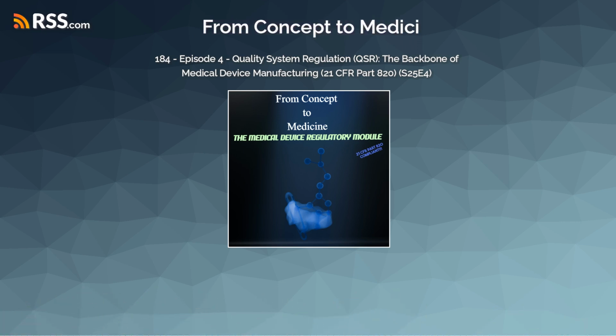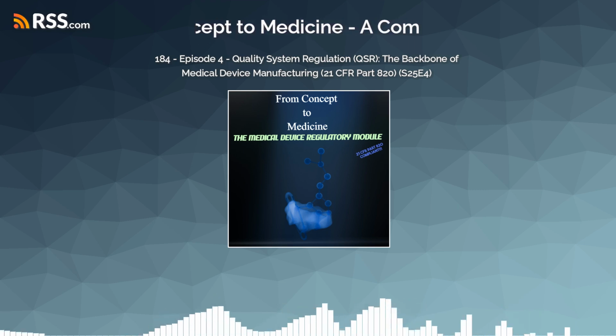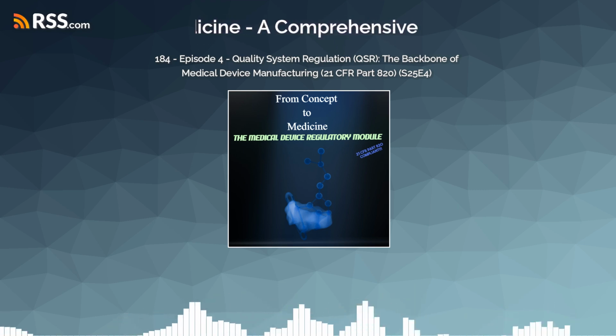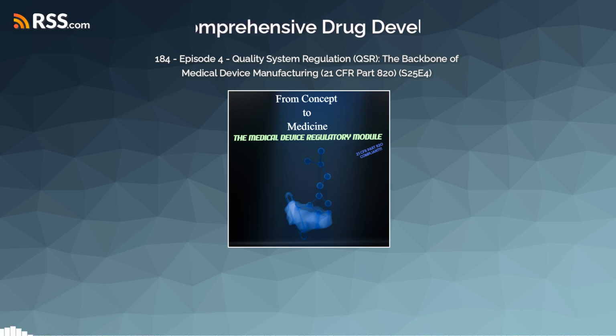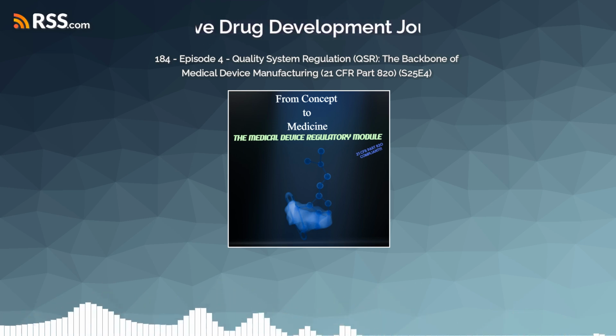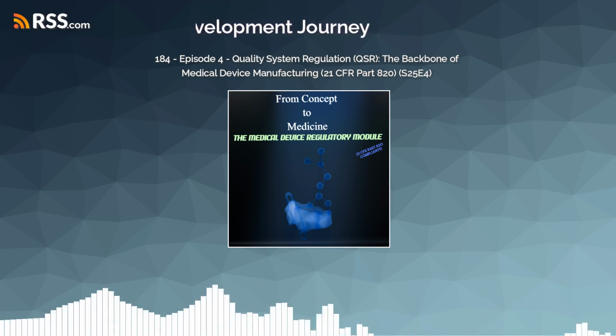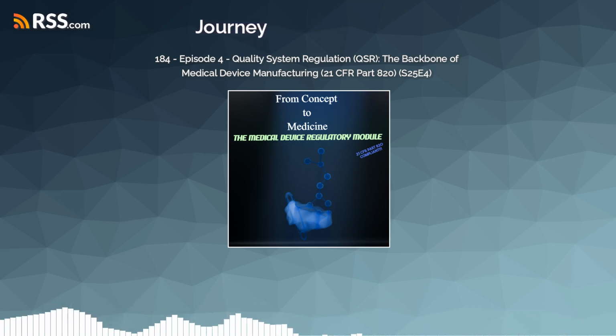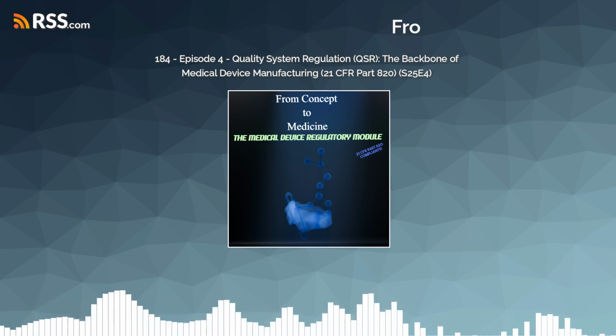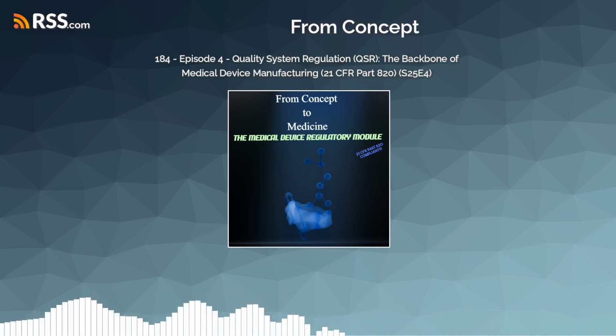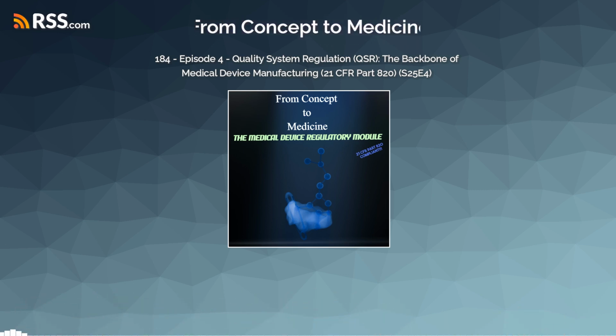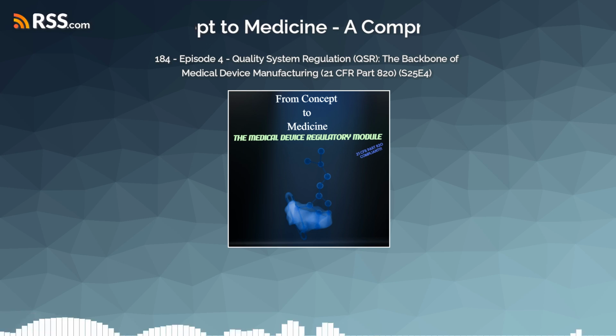Makes sense. So QSR doesn't stop at the factory door then. What about installation and servicing? Nope, it keeps going. If you make a device that needs installation, think complex imaging equipment, you need to provide adequate instructions for installation and inspection, and test procedures too, to make sure it's installed correctly and will perform as intended. A perfect device installed badly can still fail.